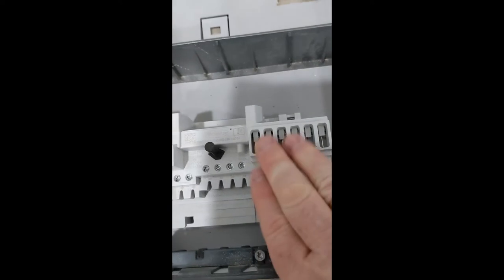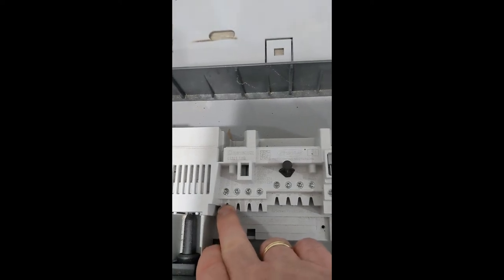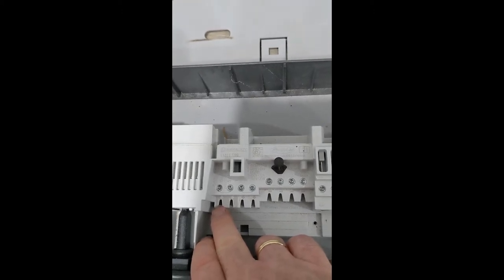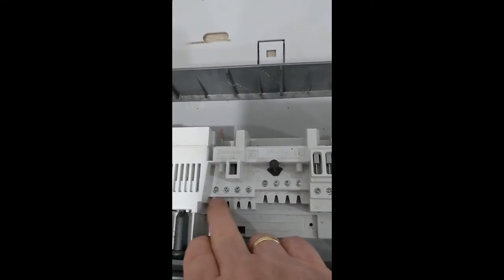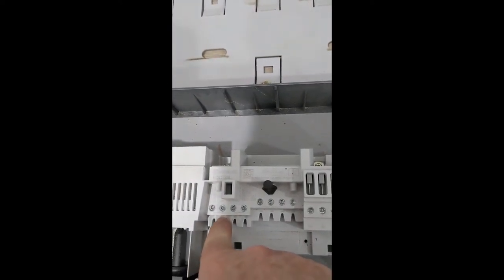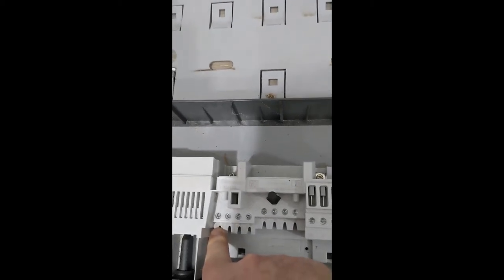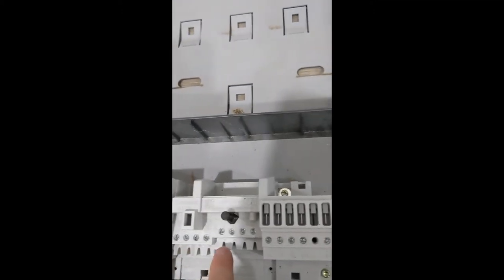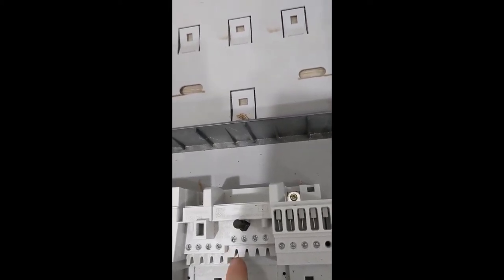In the installed unit, we should have DC input number one occupied. Because we've only got 10 panels on there, you wouldn't think this one would be occupied. It just gives you a bit of extra capacity to install multiple strings. The first string — we've only got the one string, which is 10 x 370W Jinkos — will be plugged into input position one positive, and DC input negative should also be occupied in the first position.